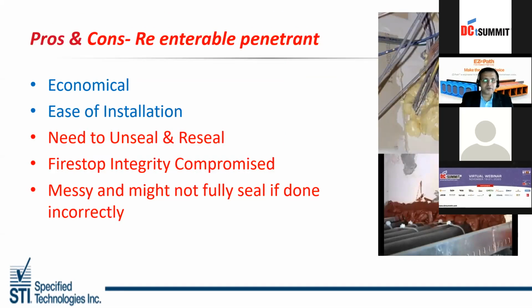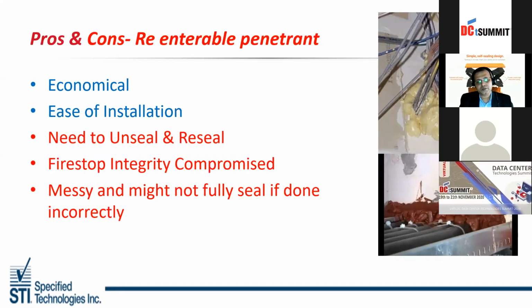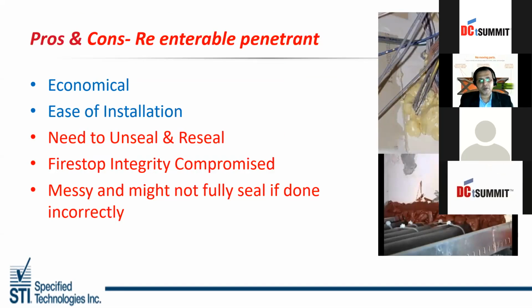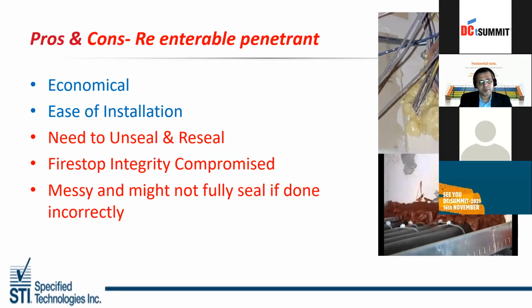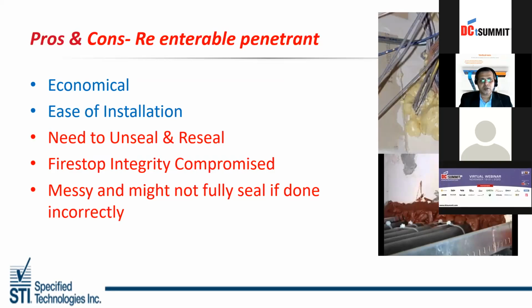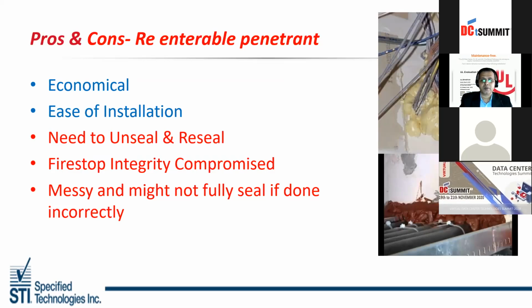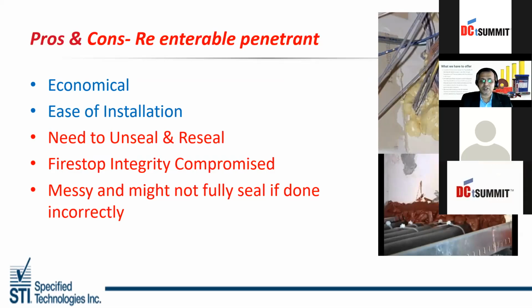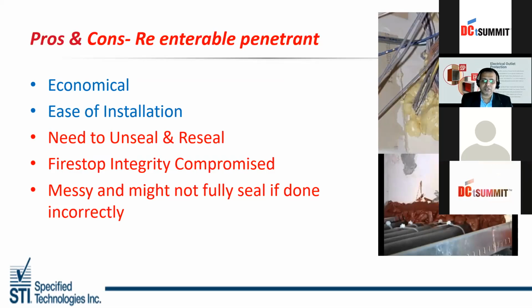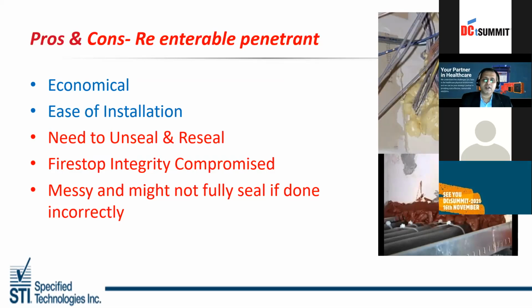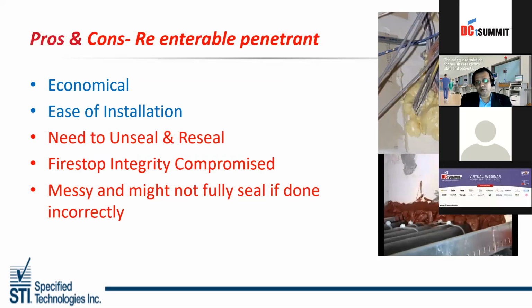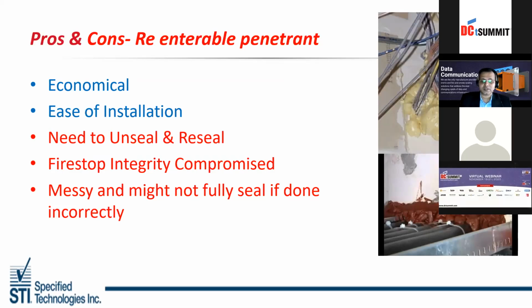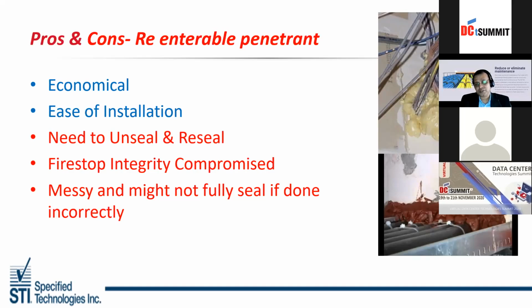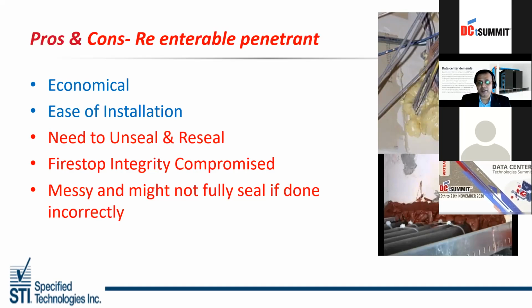Pros and cons of re-entrable penetrations. Yes, there are scenarios wherein we feel that using a putty or a foam can be beneficial for re-entrable solutions. Here I would say that when a fire stopping person is not there, the cable guy or the facility team comes in, changes the cables and goes. So the application of the sealant or the putty has to be proper in accordance with the UL tested systems. When it says 13 mm or 16 mm thickness of sealant or putty, that has to be installed.